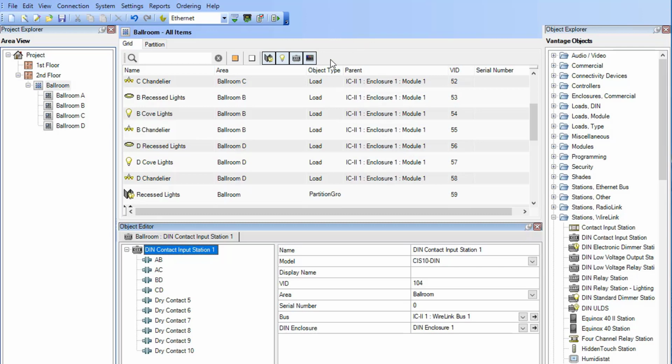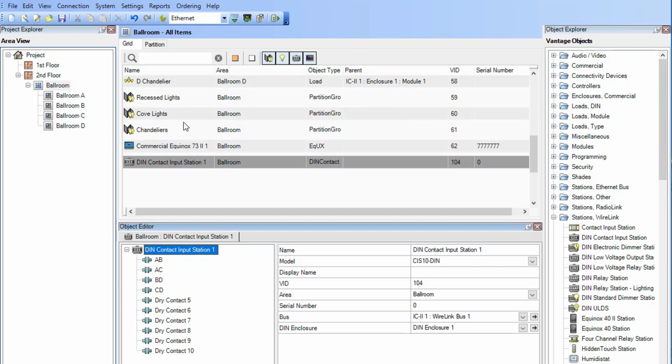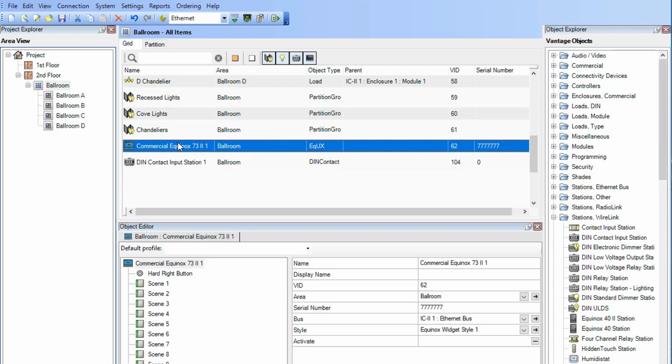So once all this is done, if I were to go now into my Equinox interface, I still have that ability with the graphic that's in there, as we've shown in previous videos, to be able to represent, change the state of each wall. That is to allow you to do some representation and tests and that sort of thing. But when it's all said and done, I would expect that you would then set it back to the current state. And then as the walls open and close, as the contacts actually change, is when the partition states will be recorded. And all of our programming then will work according to the current wall configuration.